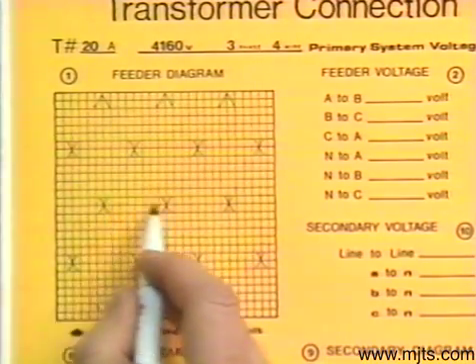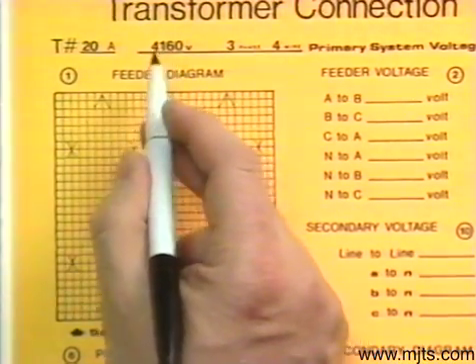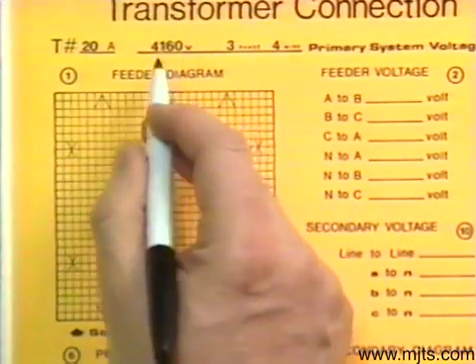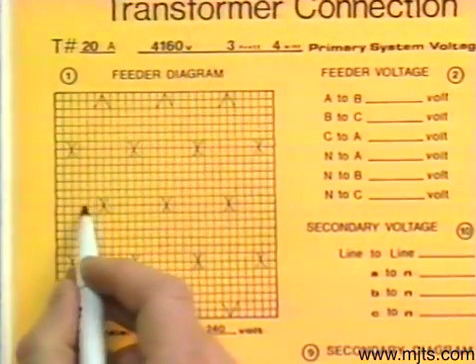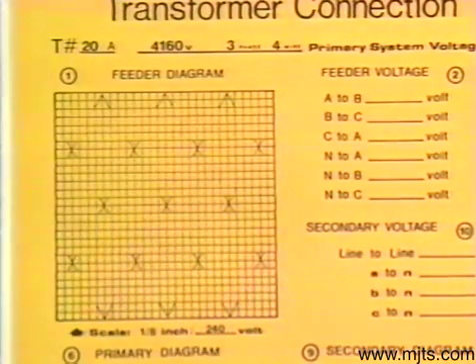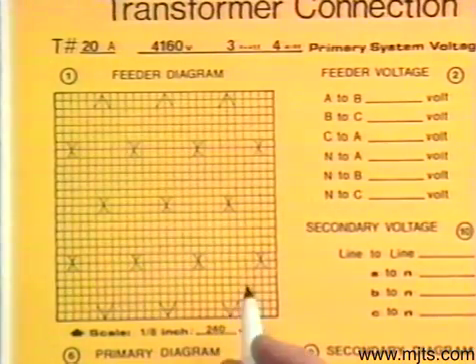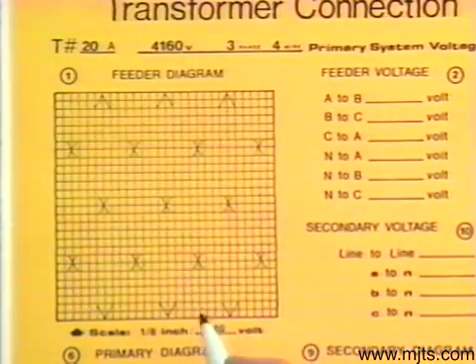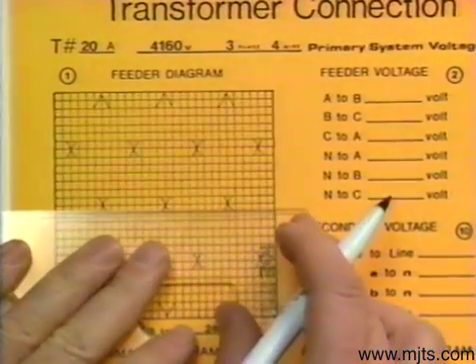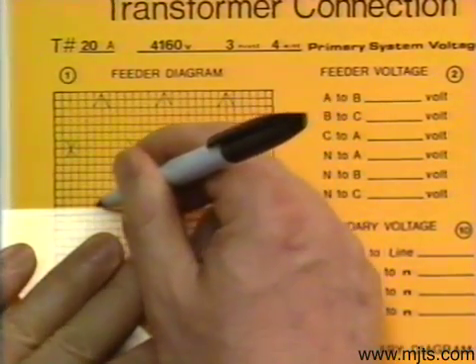The phase-to-neutral value on a 4160 system is found by dividing 4160 by 1.73, which gives us 2400 volts per vector to neutral. If I divide 240 into 2400 volts, it goes in 10 times — that's 10 eighths, or one and a quarter inches. So I'll have an inch-and-a-quarter vector for each of my phases.